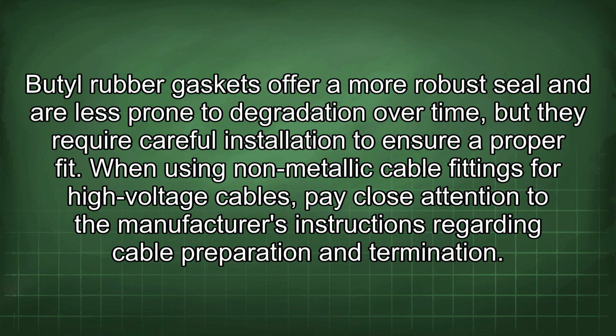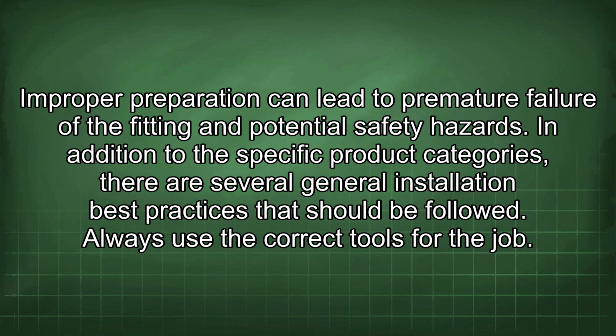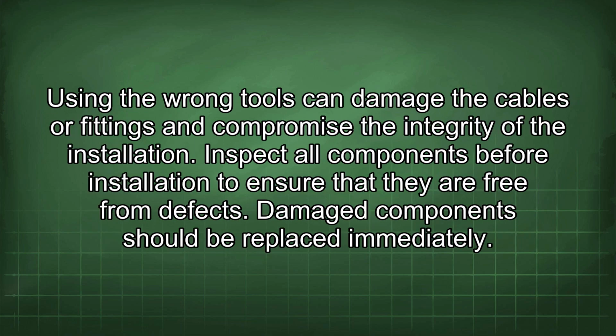When using non-metallic cable fittings for high-voltage cables, pay close attention to the manufacturer's instructions regarding cable preparation and termination. Improper preparation can lead to premature failure of the fitting and potential safety hazards. In addition to the specific product categories, there are several general installation best practices that should be followed. Always use the correct tools for the job. Using the wrong tools can damage the cables or fittings and compromise the integrity of the installation.